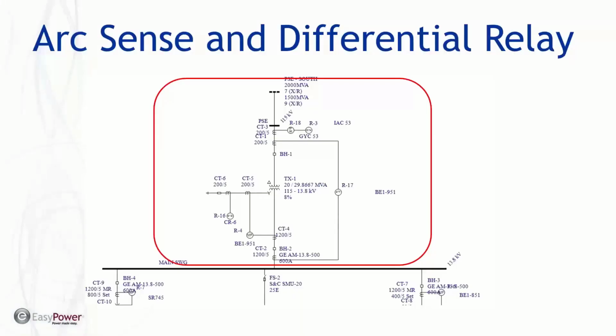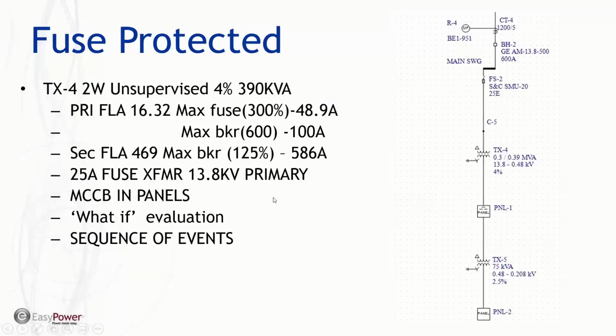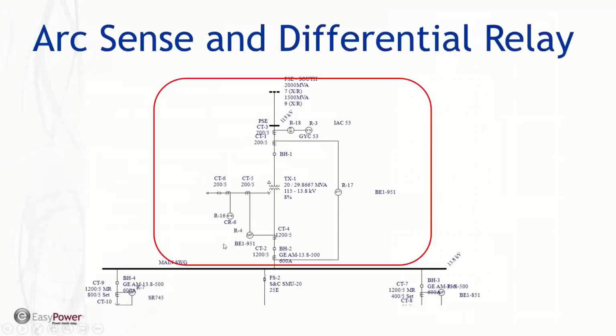I want to talk briefly on arc sense and differential relaying, which in this particular case, we have R17 set up as a differential relay primarily for the transformer. Now it's worth saying that we can include these downstream feeders if we had CTs set up, or set up the relay to consider the nulling of the total current outflow from the switchgear. So this can be a relay differential, a bus differential, or a ground differential. It can have multiple adjustments in the setting.